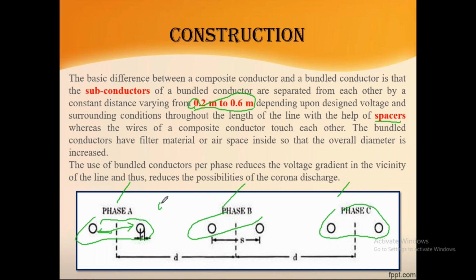And this value varies, some conductors having 0.2, some 0.4 and so on. So it is in between 0.2 and 0.6, and this value depends on how many subconductors we are using and what the voltage capacity is. Based on that we can keep the distance, that is 0.2 or 0.4, 0.6 like that. So this is the distance we have to keep between the two subconductors in the bundle conductors. And one more thing, the bundle conductors have filler material or air space. Generally we are using air space inside, so that the overall diameter is increased. If you keep the air space in between these two, the diameter will automatically increase.